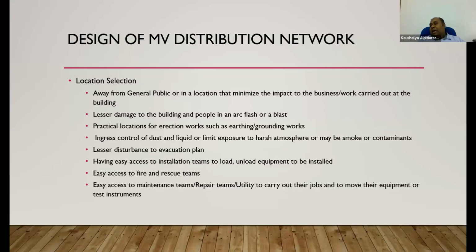Lesser disturbance to the evacuation plan. Right. What is an evacuation plan? In an emergency, we have an emergency exit plan in a particular building. If you are locating your medium voltage system along this evacuation path, and the evacuation has to happen because of the failure of medium voltage switches or loads, then you are in danger. The medium voltage switch room is on fire, and your people need to evacuate just next to that particular room. So that has to be considered during your localization of switch rooms.